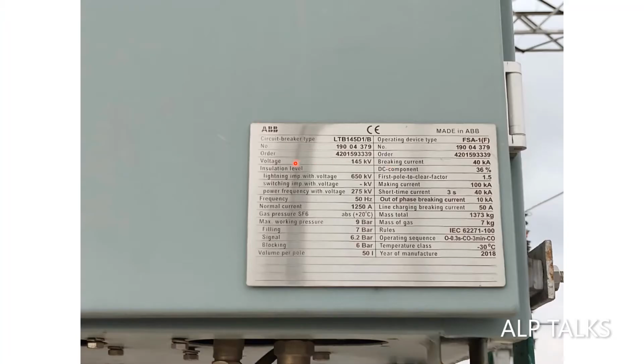Circuit breaker. So this is 145 kV, 650 kV BIL, power frequency 275 kV, 50 Hz, 1250 amp normal current. Gas pressure at 20 degrees centigrade, SF6 is there. So maximum working pressure 9 bar. Filling 7 bar, signal 6.2 bar, blocking 6 bar. Volume per pole 50. Breaking current 40 kiloamp, DC component generally 36%.